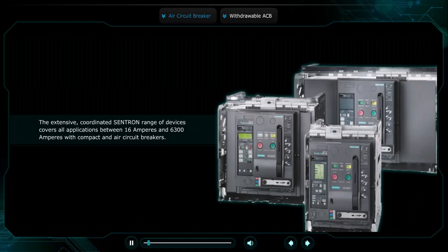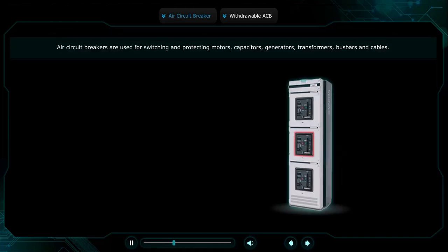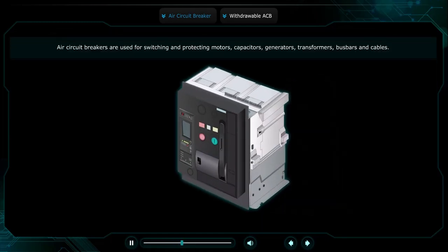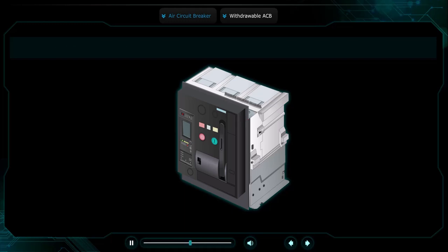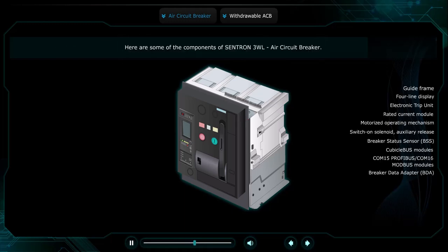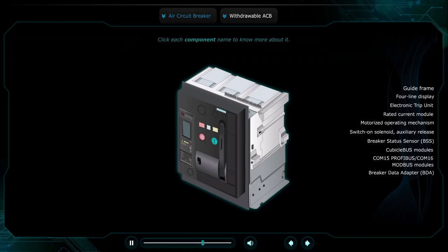The extensive coordinated SENTRON range of devices covers all applications between 16 amperes and 6300 amperes with compact and air circuit breakers. They are used for switching and protecting motors, capacitors, generators, transformers, bus bars and cables. Here are some of the components of SENTRON 3WL air circuit breaker. Click each component name to know more about it.